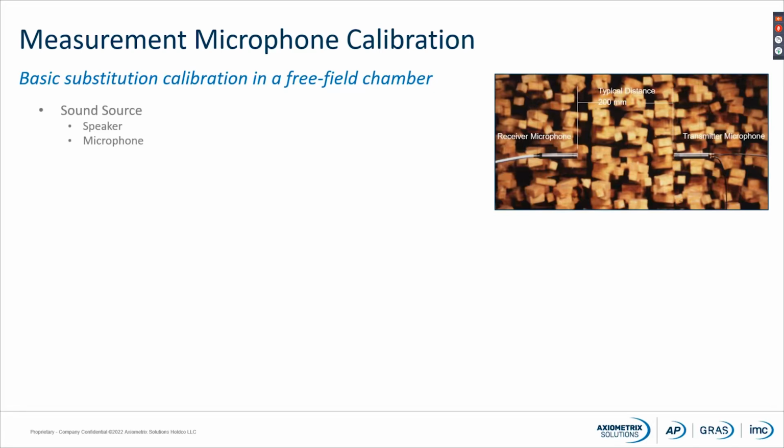If we look at comparison calibrations done in a free field chamber, we need a sound source. The sound source could be a speaker or a microphone. The reference microphone is a microphone where we have a very well-known free field response. And then we need, of course, our microphone under test.